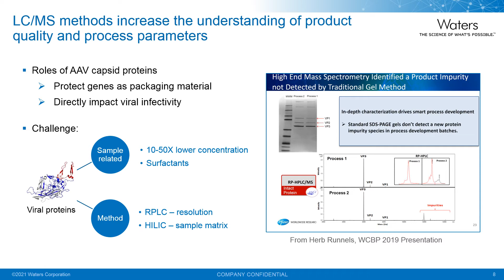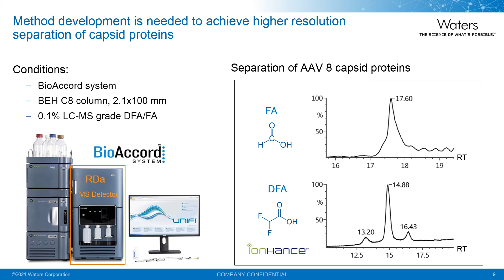The method development work was done on the benchtop LC-MS instrument called BioAccord, starting from the gold standard method, where we're using a BEH C8 column with 0.1% formic acid. We can see that there is no separation between the VP proteins, and they're also co-eluting with the detergent or surfactant. So switching the mobile phase from formic acid to difluoroacetic acid, which is another mobile phase modifier, we found that the peak shape is improved and the resolution is also increased.